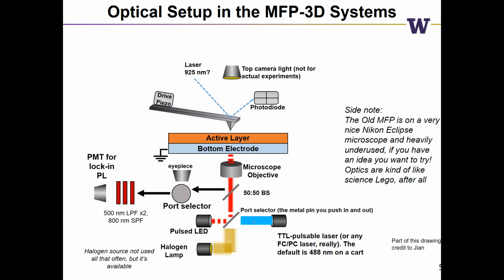So regardless of which light source you choose, it bounces into the AFM. There is a 50-50 beam splitter. There is also a full mirror, so 100% beam splitter, 100-0, I guess, if you want. But by default, it's 50-50. It goes through the microscope objective and focuses on the sample, and then some amount of light comes back through the port selector. By default, the port selector is on the eyepiece, so that way you can actually see what's going on. You could also change it to go through the PMT on the left side.